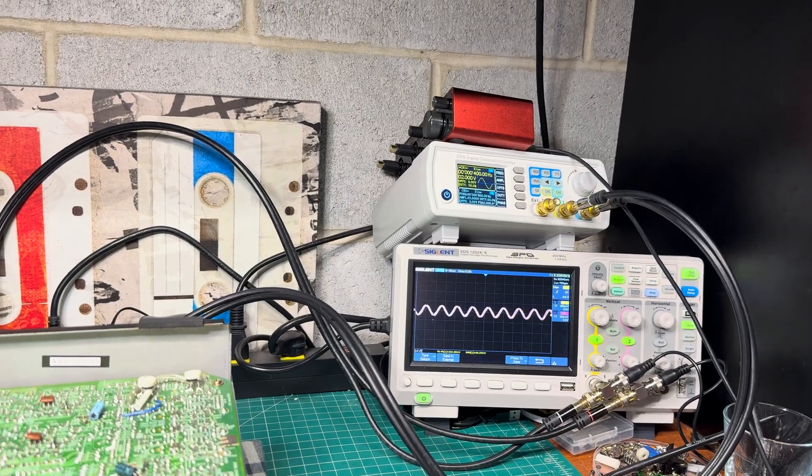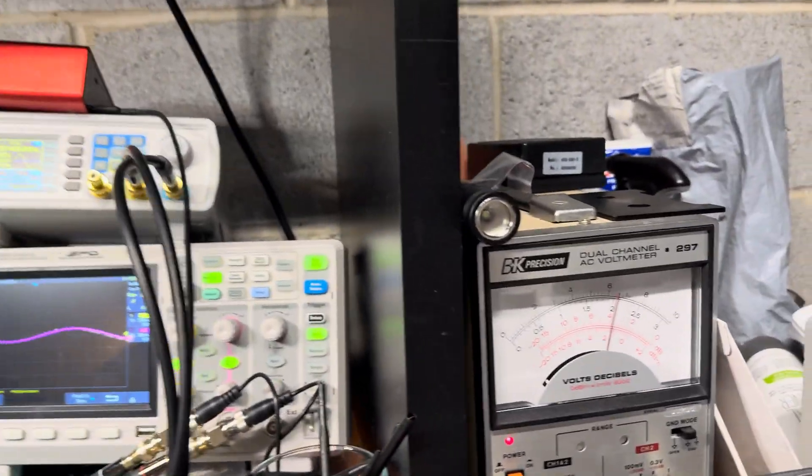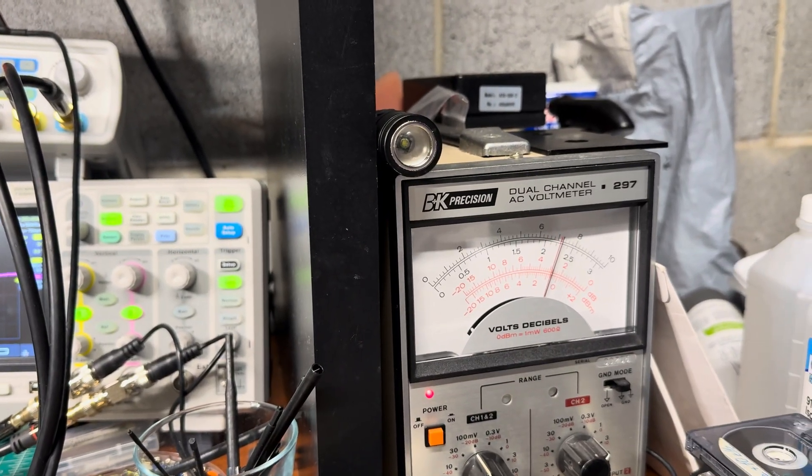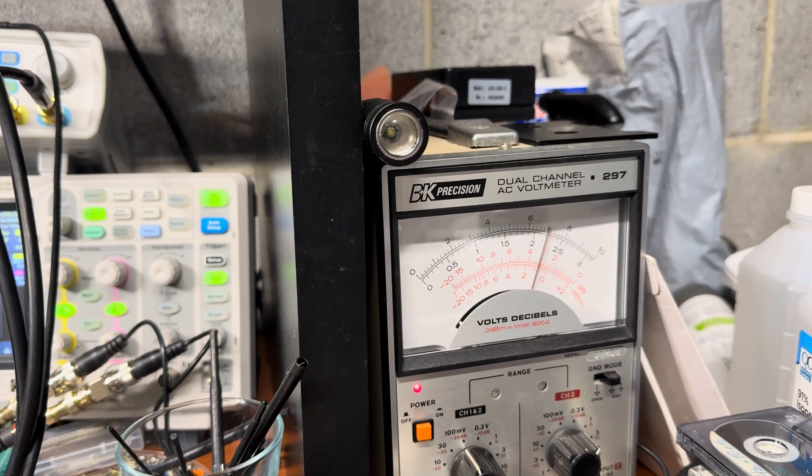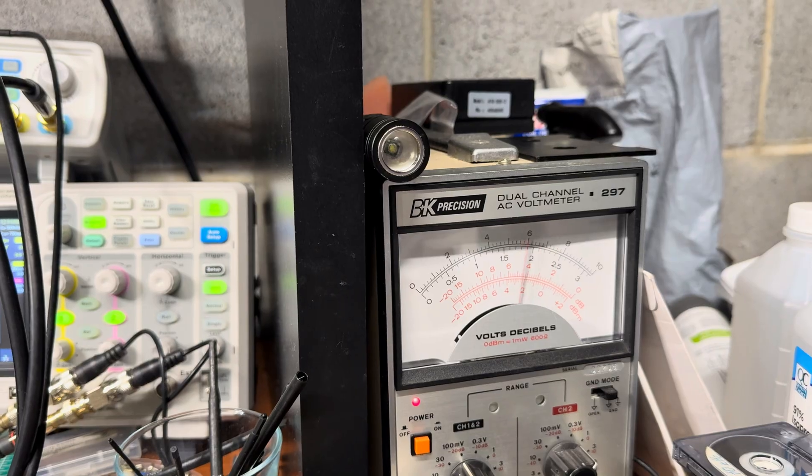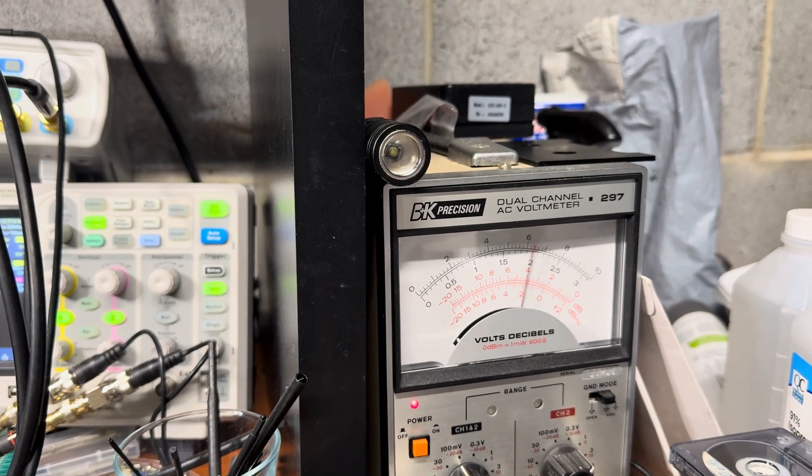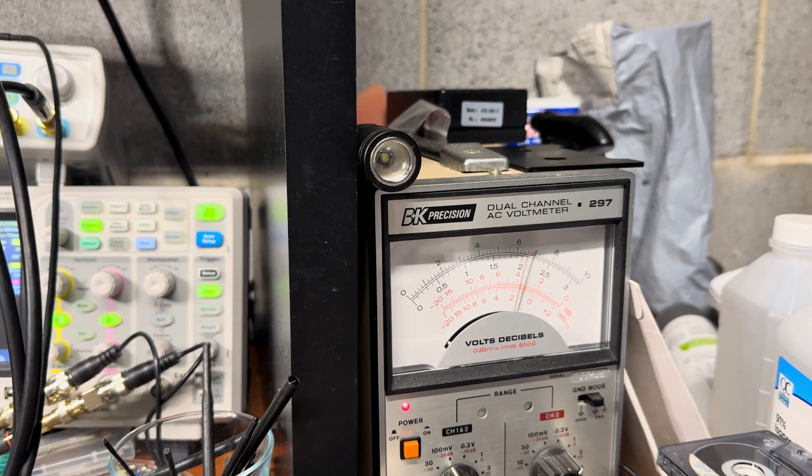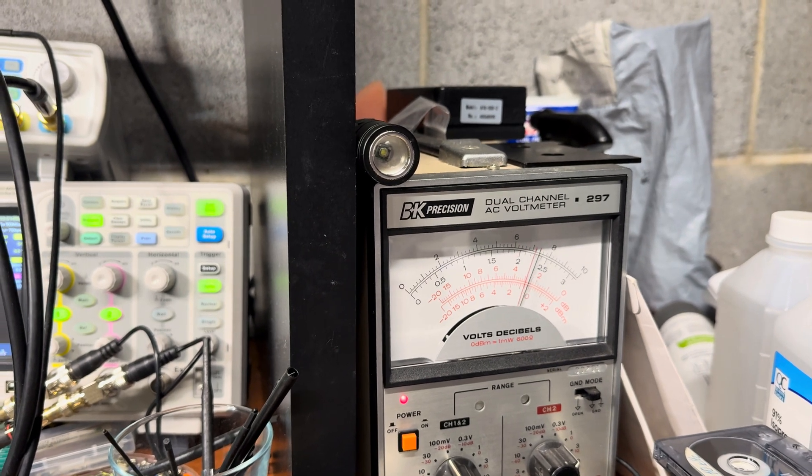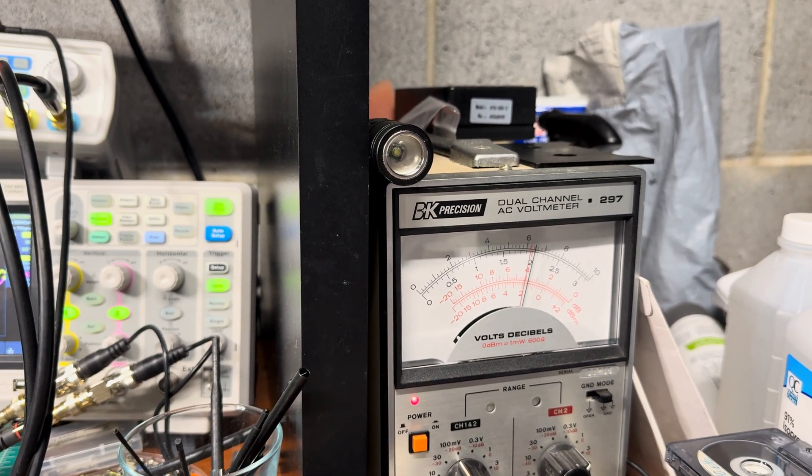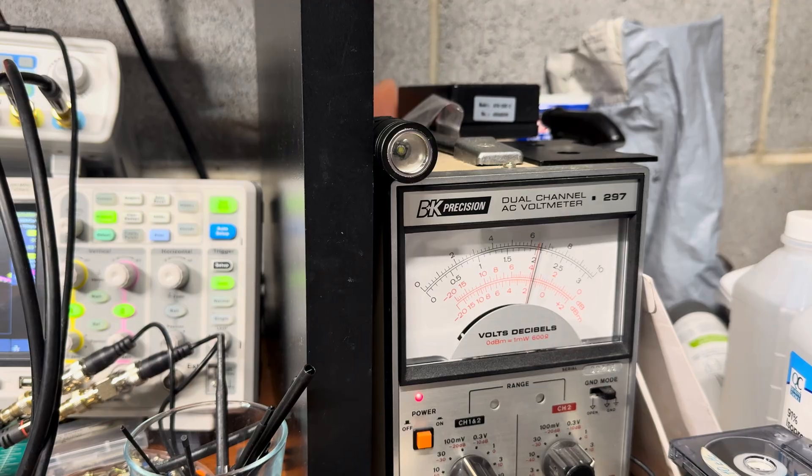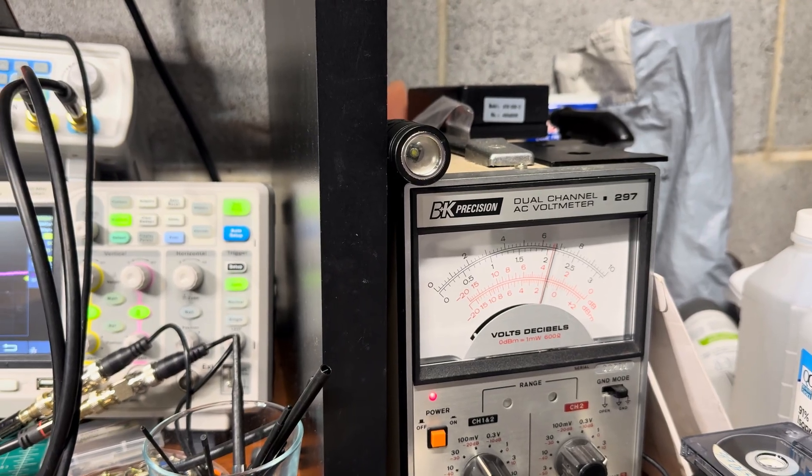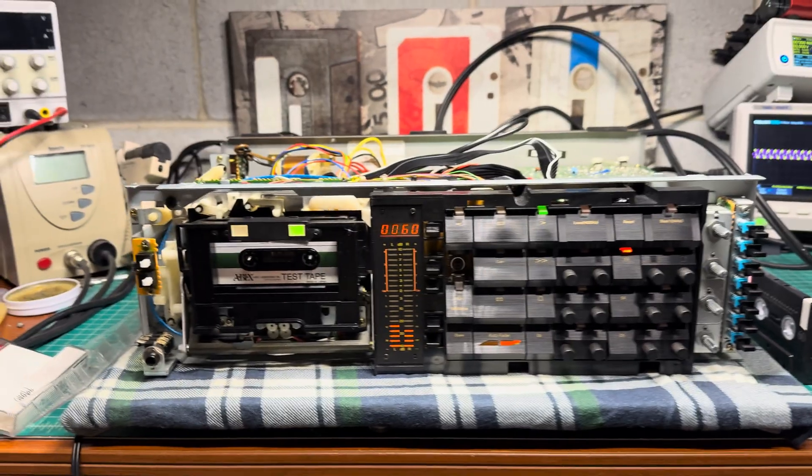It's found the azimuth, good. And that's the levels. It's one kilohertz, 250, 12.5. It tries to find azimuth and see how high it is. Now that's azimuth search works. 10 kilohertz, 6.3, a little bit lower. 1 kilohertz, and 250 again, high. Really good results.